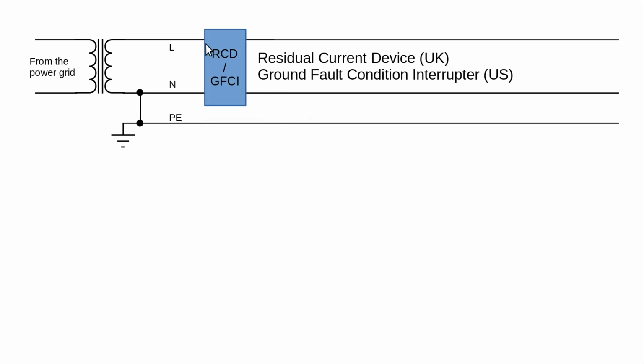Well, it would be a waste of copper, but we use a separate device in here, which is an RCD or GFCI. RCD and GFI or GFCI, they're the same thing. One is just the UK name and the other one is the US name. And what this device does is it monitors the current going through here and through here, and it checks whether the current is exactly the same. It really has to be very close, up to only a few milliamps. And if there's too much of a difference between power going through here and power coming back there, then the device will trip and open up the circuit.